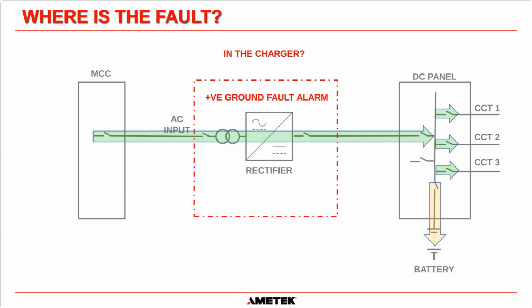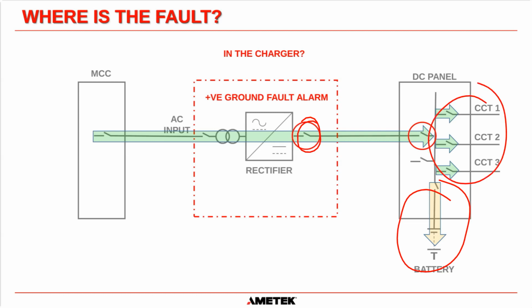Okay. So the first thing is, is it in the charger itself? That's what a lot of people think. Oh, the alarm's on the charger, so the fault must be in the charger. That couldn't be further from the truth, but we will look into that. So if you think that the fault is in the charger, or if you are just looking for a ground fault, this is a step that you should be taking. First thing to do is to isolate the charger, okay? And to do that, the first thing I would do is open the output breaker on the charger. You still have your battery available if it's connected like this circuit here. So your load circuits will still remain powered, okay?